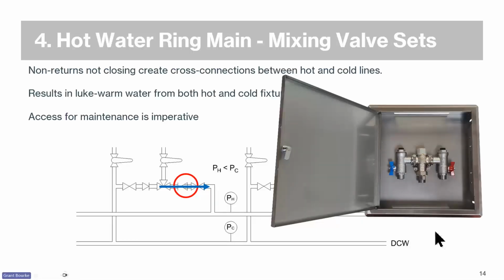You can put them in the ceiling above doors and toilets or bathrooms, in the backs of cabinets, in wardrobes on an adjacent room. You just need to talk to the customer and get a bit tricky about where you're going to install these valves. But you really want to put them somewhere that you can get at them, because at some point, some poor sod's going to be trying to find these things to clean out those non-returns and get them going again.